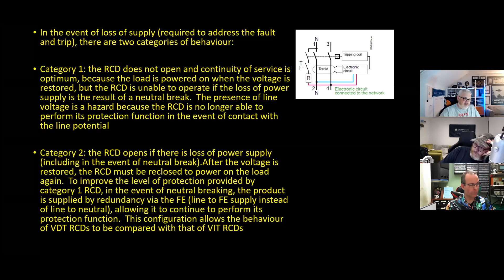Category 2 is the RCD opens if there's a loss of power supply, which I like straight away, including in the event of a neutral break. Good. After the voltage is restored, the RCD must be reclosed to power on the load again. That's why I said latching, non-latching. To improve the level of protection provided by category 1, in the event of a neutral break, I'm talking about broken PENs here, the product is supplied by redundancy via the functional earth, line to FE supply instead of line to neutral, allowing it to continue to perform its protective function. This configuration allows the behavior of a voltage-dependent type RCD to be compared with that of a voltage-independent type RCD. Now, if that hasn't melted your brain, I don't know what does.